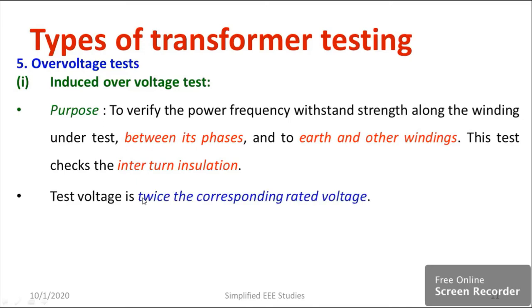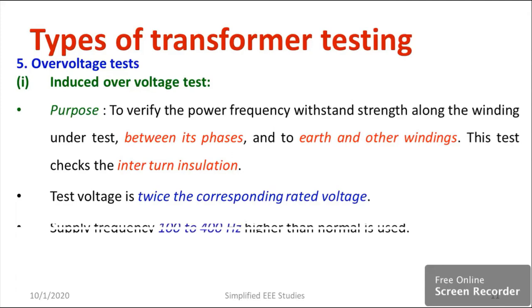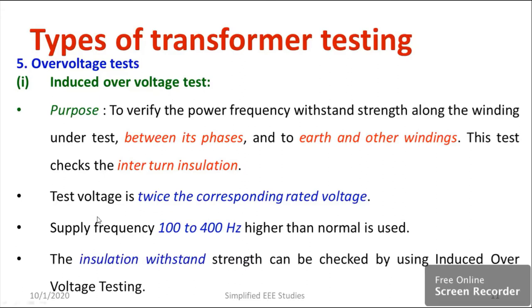The test voltage should be twice the rated voltage — so if the rated voltage is 200 V, you need to apply 400 V. The frequency can also be varied from 100 to 400 Hz — higher than normal. The insulation strength is checked under these conditions, and the winding insulation should not show any disturbance. If disturbance is found, the quality of inter-turn insulation is not sufficient and must be replaced.